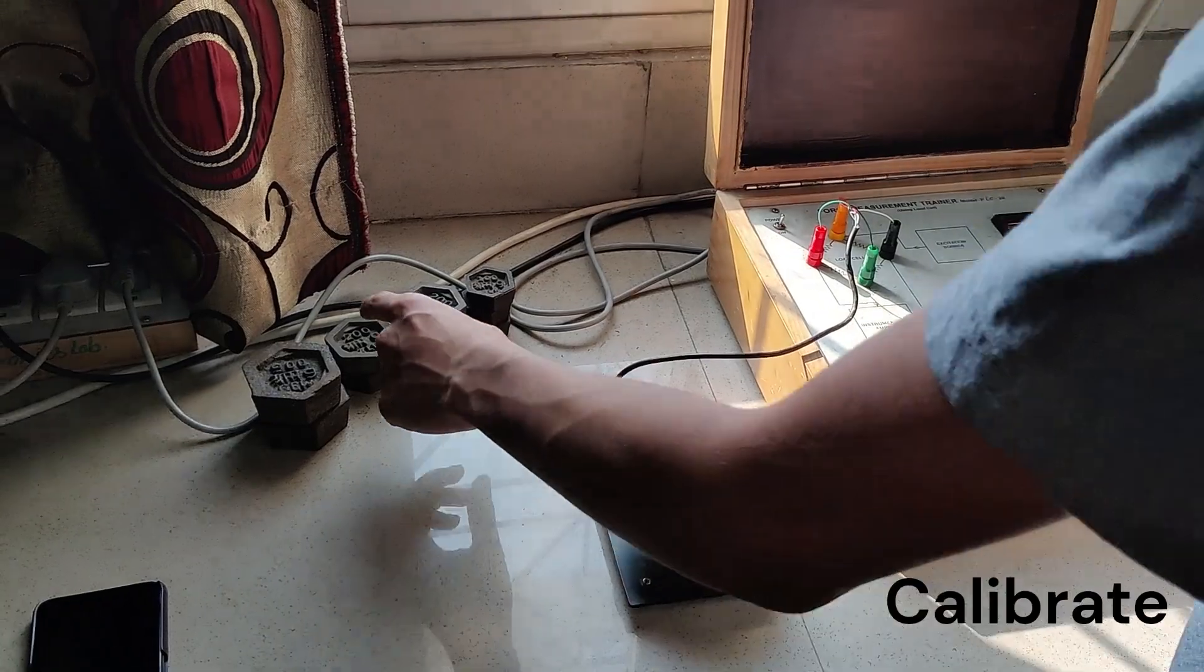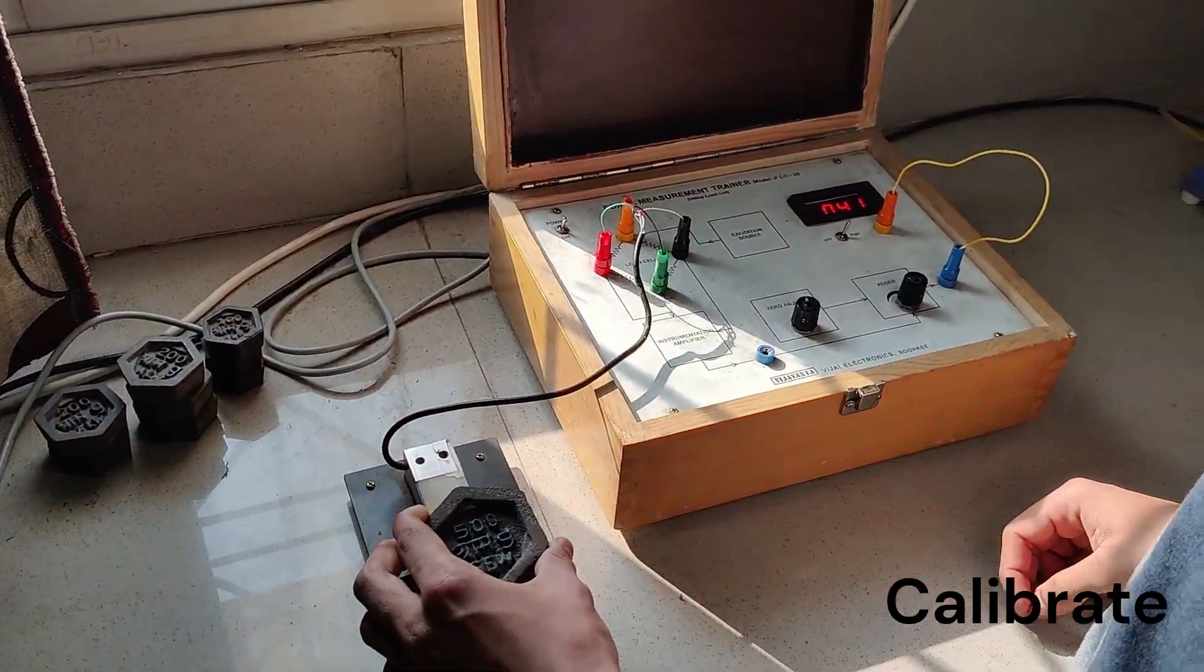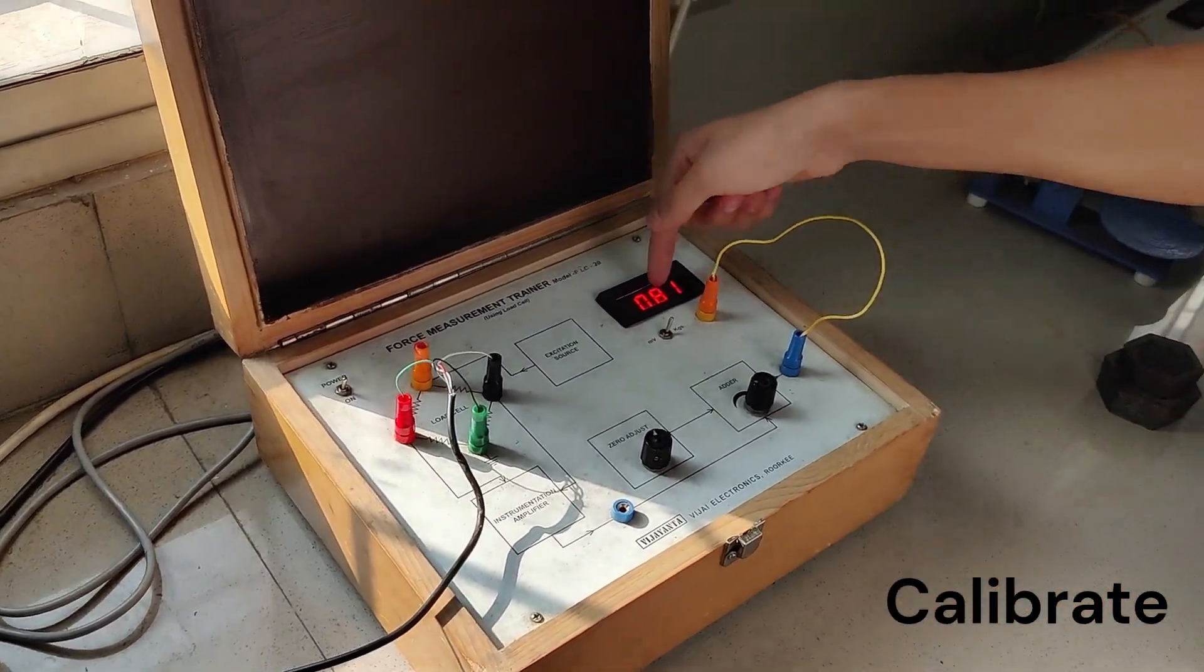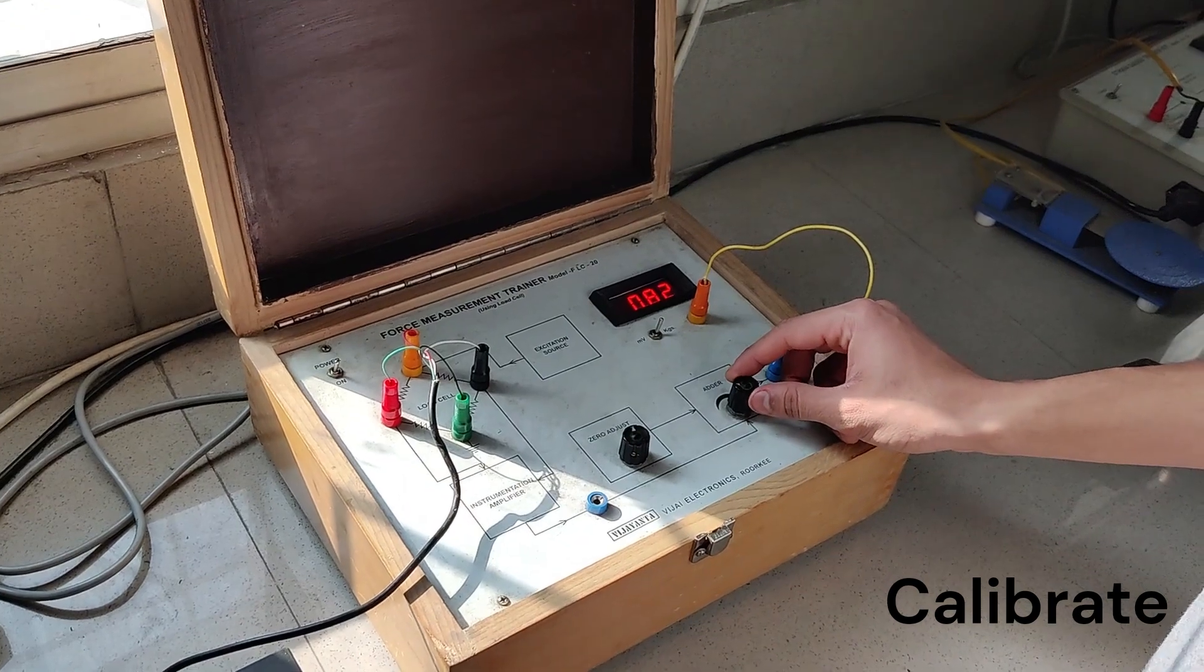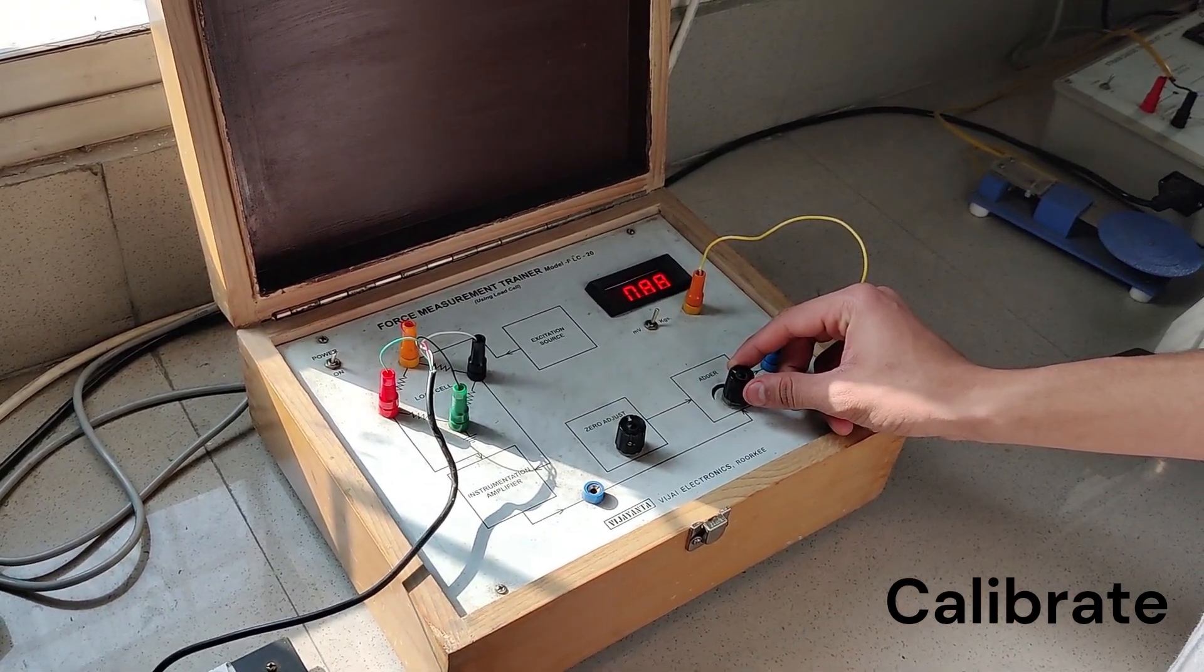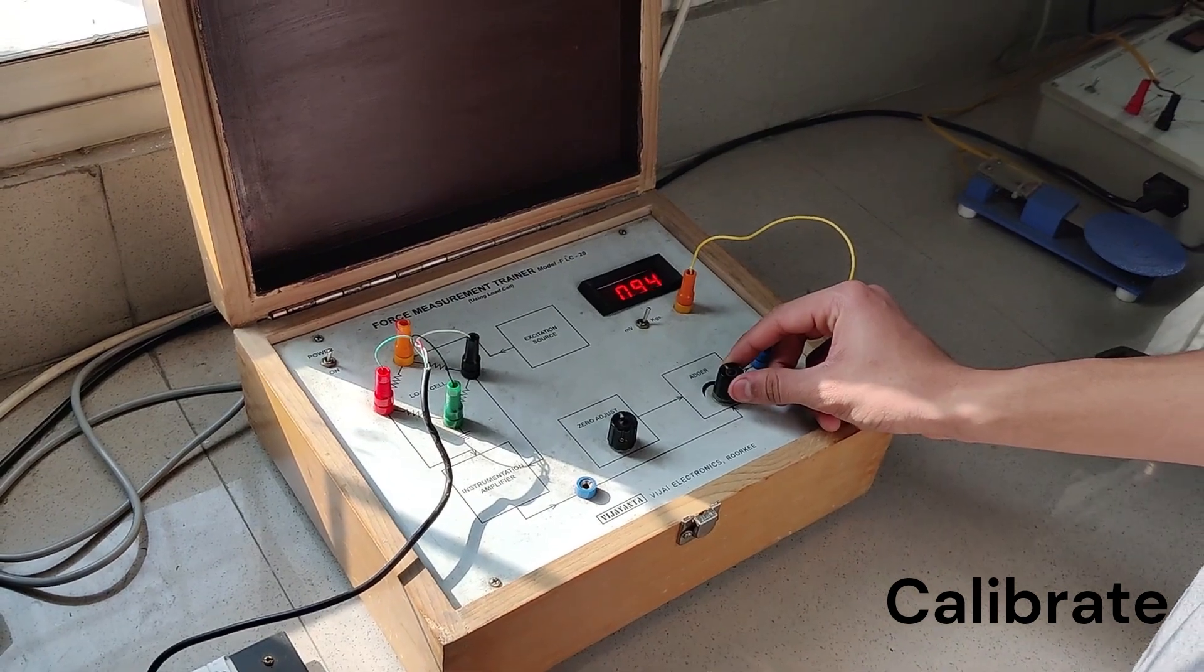The second step is to calibrate the load cell by putting 1 kg load on the load cell. The reading is 0.81 but it should be 1, so calibrate it by turning the adder knob. Now it is calibrated.